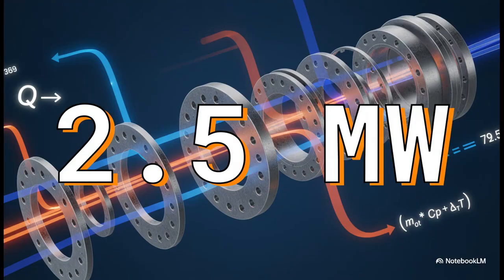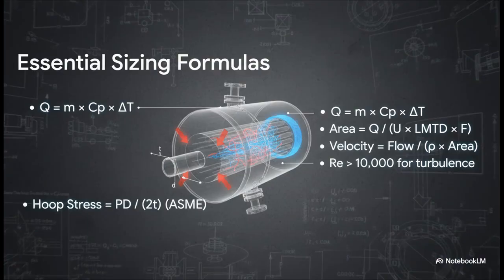The first and honestly most important number is our heat duty, which we call Q. Based on our flow rates and temperatures, we need to move 2.5 megawatts of thermal energy from the crude oil over to the cooling water. This number drives absolutely everything else in the design. And this right here is our core engineering toolbox. We use that heat duty and our corrected LMTD to figure out the surface area we need. Then we double-check that our fluid velocities are high enough to create turbulent flow. That means a Reynolds number over 10,000, because that's essential for good heat transfer.